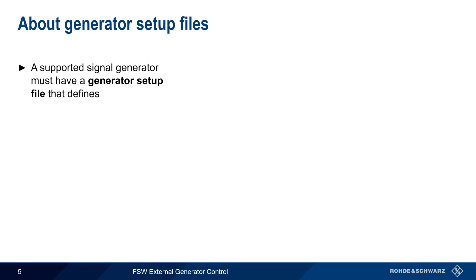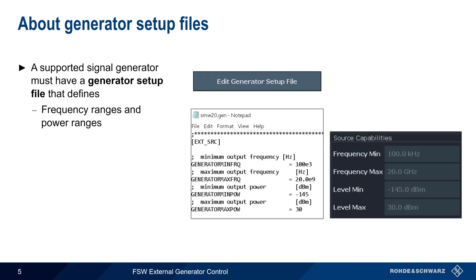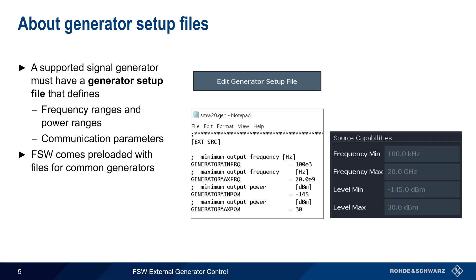Supported signal generators must have a generator setup file. This is a plain text file that can be viewed or edited by pressing Edit Generator Setup File. Generator setup files define both the frequency and power ranges supported by the generator, as well as communication parameters. The FSW comes preloaded with setup files for many common analog and vector signal generators, but setup files can also be created and/or modified to support other instruments.